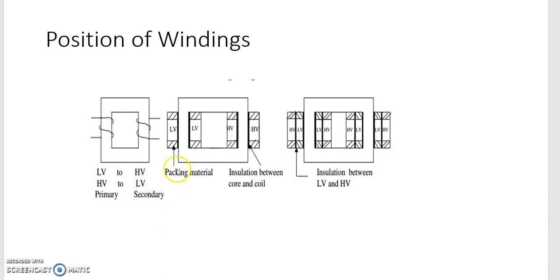As also discussed in module 1, the position of the windings with respect to its core is important. Unless otherwise specified, the low voltage winding is always placed next to the core and the high voltage winding over the low voltage winding, in order to reduce the quantity of insulation used and avoid the possibility of breakdown in the space between the core and the high voltage coil. In some cases, the high voltage coil is placed next to the core.